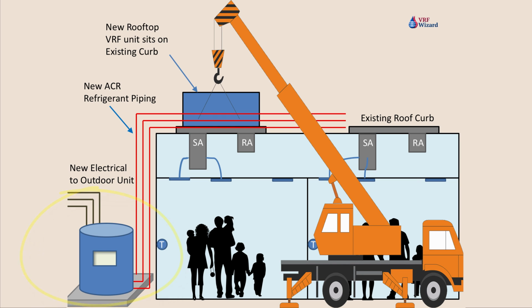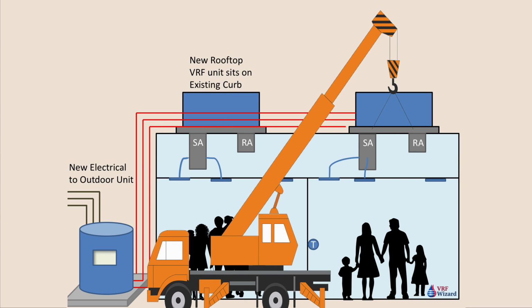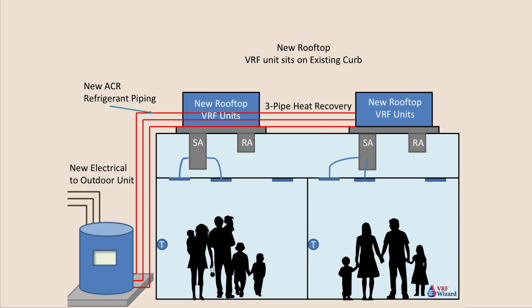In this new packaged VRF rooftop unit, you will have your evaporator coil, your fan, and your controls, and you'll have the new distribution box or branch selector box, or whatever the manufacturer is calling their heat recovery exchange box. So no longer will that be located inside. All this is contained within that one unit. So you just run the pipe up there and connect the pipes to the rooftop package VRF unit. You just keep replacing those right onto the existing curb, and then connect the ACR refrigerant piping to the new units, charge it, start it up, and this prevented you from having to do any of the work inside.